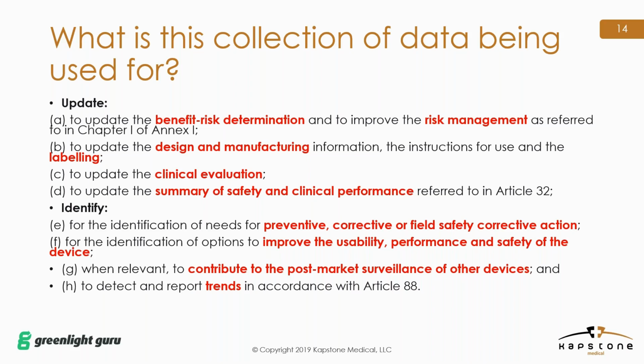As shown on the previous slide, under the data sources, experience with similar devices is considered a proactive data source for post-market surveillance. So the data that you're collecting for one device can contribute to the post-market surveillance data of another device. And then lastly, this information that you collect is going to be used for trend reporting, which I will touch on a little bit later. So depending on the outcomes of your updates, your identifications, and things like that, you're going to update technical documentation accordingly. And again, I'm going to touch on that a little bit later, on what type of technical documentation. So now you're starting to get an idea of these new requirements. If you look at some of what I've highlighted: design and manufacturing, labeling, risk management, preventive or corrective actions, trending. So you're starting to get an understanding of, okay, how am I going to incorporate this into my quality management system, and what processes may be interrelated.